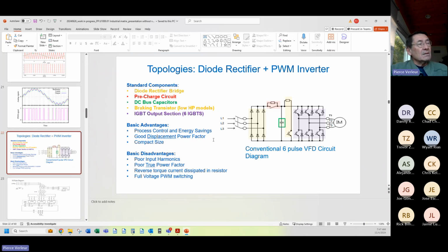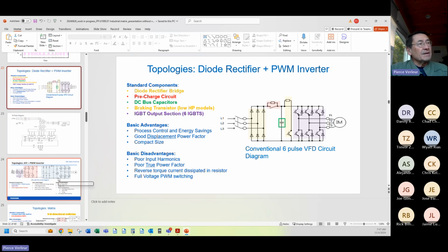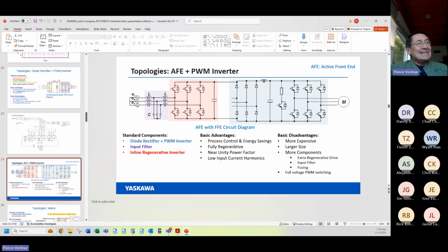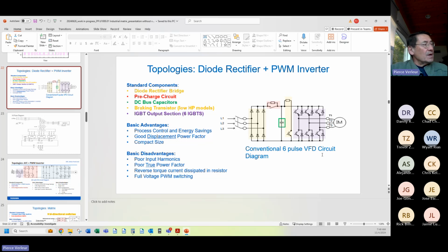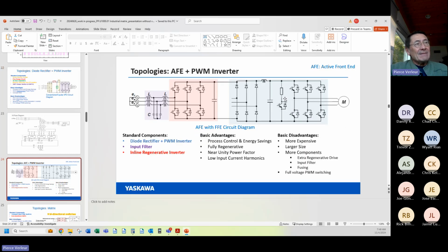He says that with 6, 12, or 18 pulse, you have to put filters here to protect the motor, but that you don't have to do it with an active front end drive. This is an active front end drive. It's the exact same circuitry going to the motor. So why, in this case, do you need filters when, in this case, with the same circuitry, you don't need filters? Obviously, that's technically not correct.